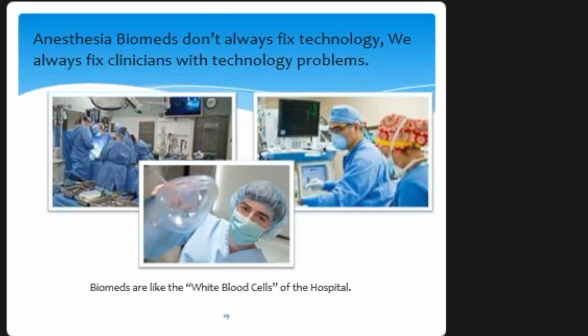And so a lot of times we have to do repairs and swap outs and things like that. In the worst case scenario with a vent failure, the whole entire machine keeps functioning except the ventilator motor. And basically, I've done these more than a few times. We have a spare anesthesia machine that we'll bring into the room that will just ventilate the patient while all the rest of the stuff on the anesthesia machine stays working. And something to think about: an anesthesia machine is a technology truck for the anesthesia MDs. The machine part, they don't always use, but all the stuff that hangs on one of these things makes their practice possible.